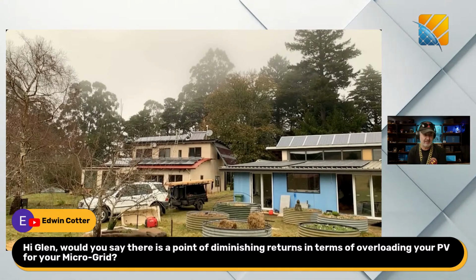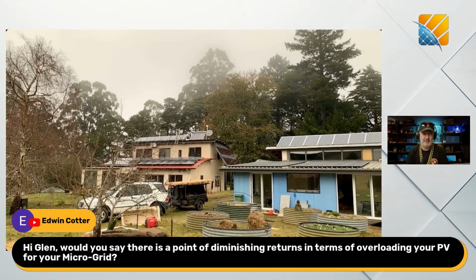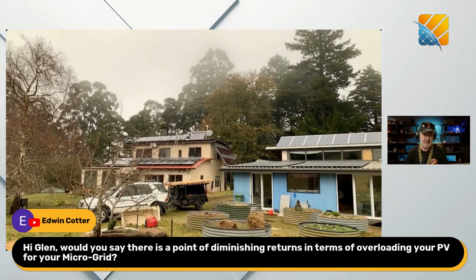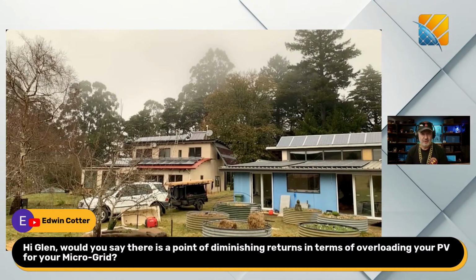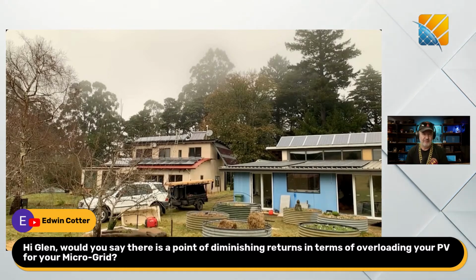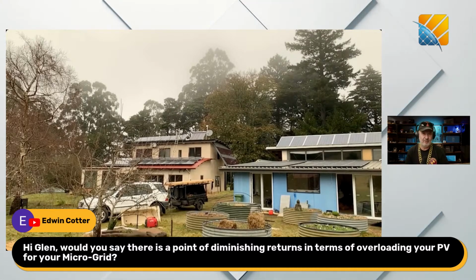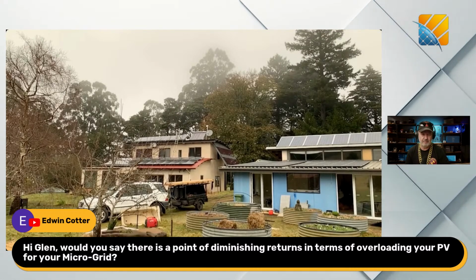So here, just to give some numbers, Edwin, we've got about 100 kilowatts of solar and a 30 kilowatt microgrid, so you could say we're more than 3 times overpowered. But because most of that is a comms-controlled solar farm, controlled directly by the battery inverter with a data cable, it can reduce its generation in milliseconds, so it can manage that huge amount of overpower potential.